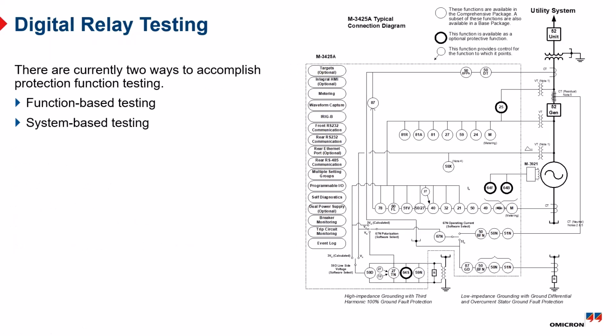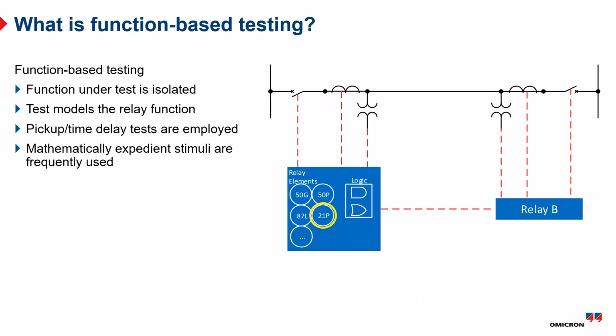As far as relay testing currently, there are two different approaches currently used. One we call function-based testing, and the other is called system-based testing. Let's talk a little bit about what this is. What is function-based testing? Remember that single line I had with all of the different protective functions on it. Function-based testing is I somehow isolate the output of that particular function. I provide a test stimulus for that function and measure the relay's response.